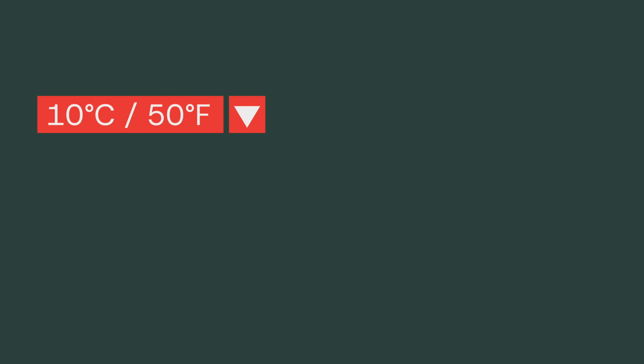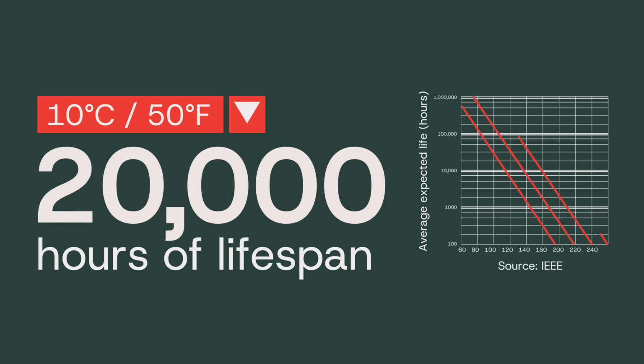The largest source of heat in an electric motor is due to your joule losses or I squared R losses. And as the name implies, it's the square of current that drives those losses. When we reduce the motor power, we reduce the motor current. As we reduce the motor current, given that that's squared, we make a dramatic reduction to the heat load inside that motor. So what does this mean? A cooler motor is going to oxidize its windings more slowly. And the rule of thumb is that for every 10 degrees temperature reduction, we've got an additional 20,000 hours on the lifespan of the motor insulation.